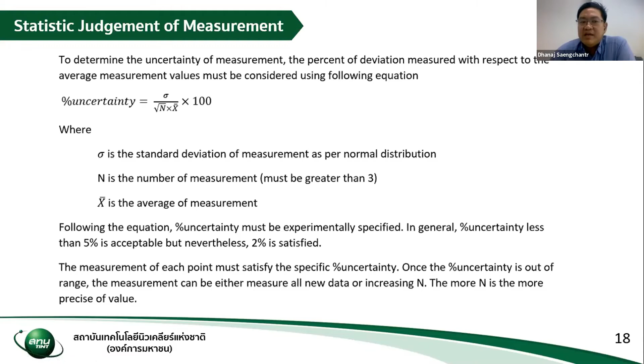If the uncertainty is greater than 5%, you have 2 choices. One is increasing the number of measurements and recalculating until the uncertainty is less than 2%, or you cancel all the measurements and restart at that point, new 3 measurements or 5 times, something like that. But if you get 2%, it is satisfactory, so it means that your data measured at that point is not so much different.